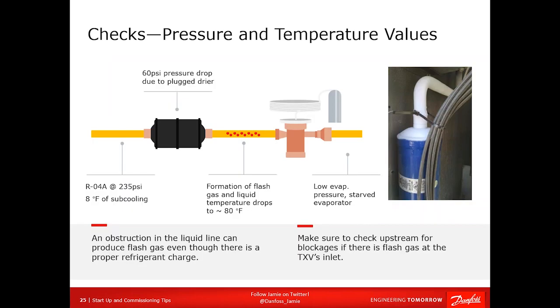All right, actual photo on the right-hand side. I get people to send me pictures all the time of stuff they see. This is not fake snow. This is actually a filter dryer doing a great impersonation of a metering device. It is plugged, and it's causing such a massive temperature and pressure drop that it is literally below freezing leaving. So what do you have? Well, you got 2 metering devices in series, the dryer and your metering device. And believe it or not, they do not work better than 1 metering device.